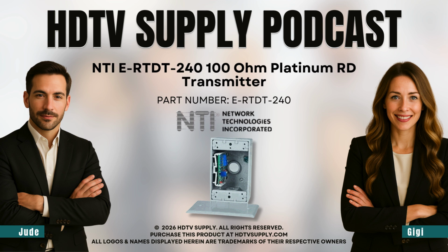Okay, now let's unpack the jargon: 100 ohm platinum and that 4-20 mA standard. If you're not in industrial automation, those are just numbers. So why 100 ohm platinum? What's special about that? It all comes down to precision and stability. The platinum element is incredibly stable over long periods, even in tough conditions, and its electrical resistance changes in a near perfectly straight line as the temperature changes. So it's predictable. Very predictable. And for this device, that gives you an accuracy within plus or minus 0.8 degrees Fahrenheit. It's a really tight band.